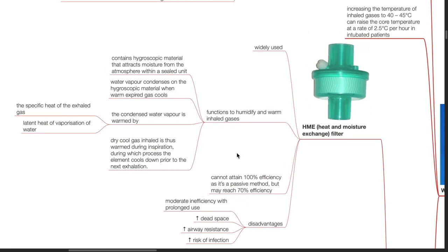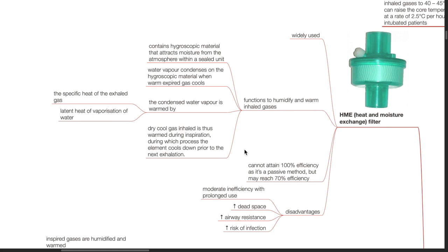Methods for warming inspired gases: the heat and moisture exchange (HME) filter is widely used — it functions to humidify and warm inhaled gases. These devices contain hygroscopic material that attracts moisture from the atmosphere within a sealed unit. Water vapor condenses on the hygroscopic material when warm expired gases cool. The condensed water vapor is warmed by the specific heat of the exhaled gas and latent heat of vaporization of water. Dry, cool gas inhaled is thus warmed during inspiration, during which process the element cools down prior to the next exhalation. HME filters cannot attain 100% efficiency as it is a passive method, but may achieve 70% efficiency.